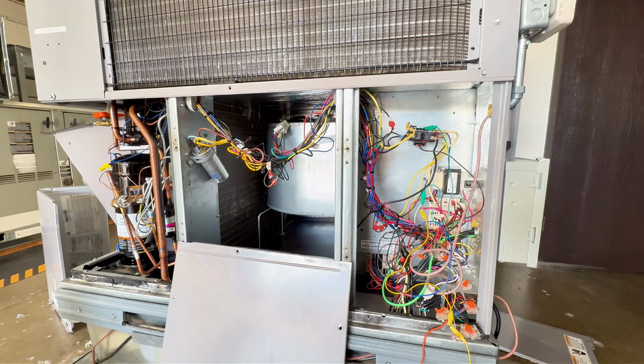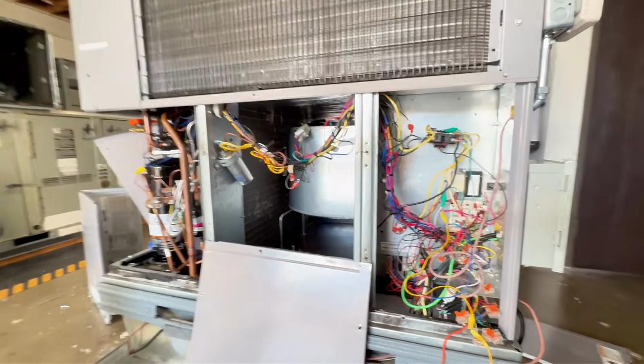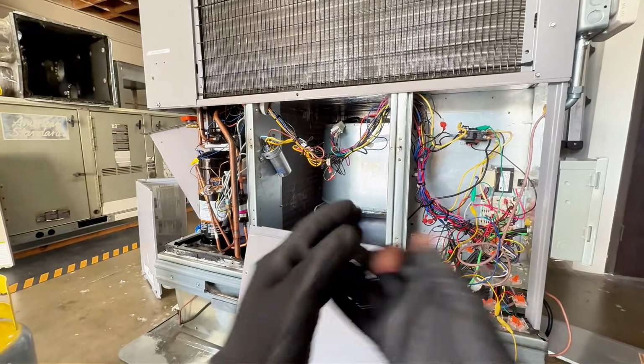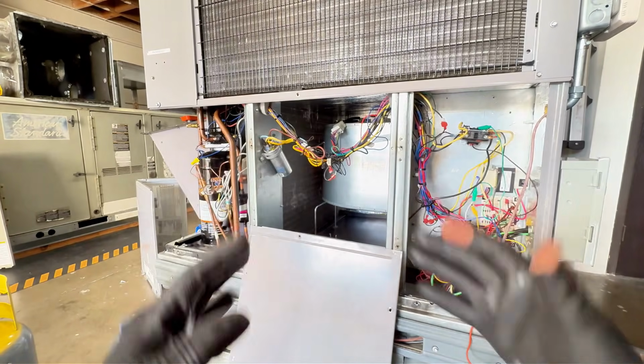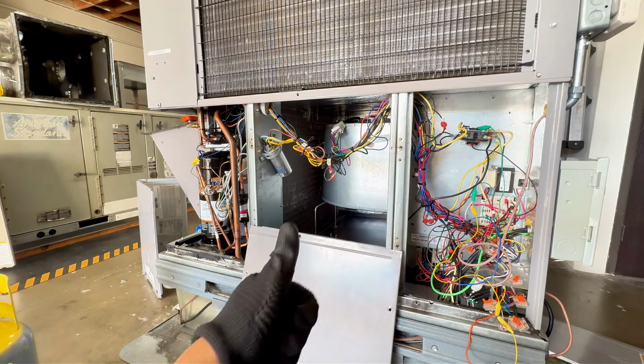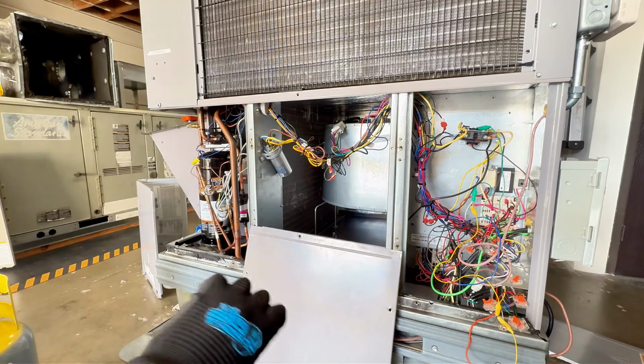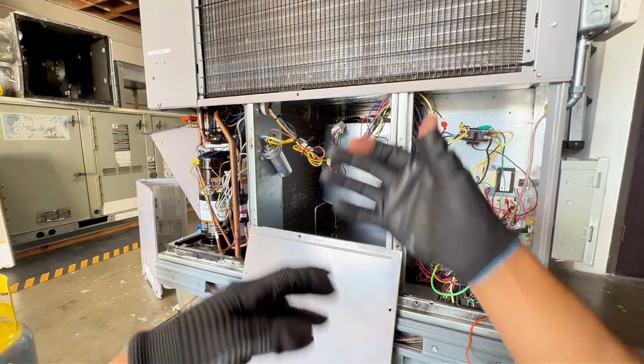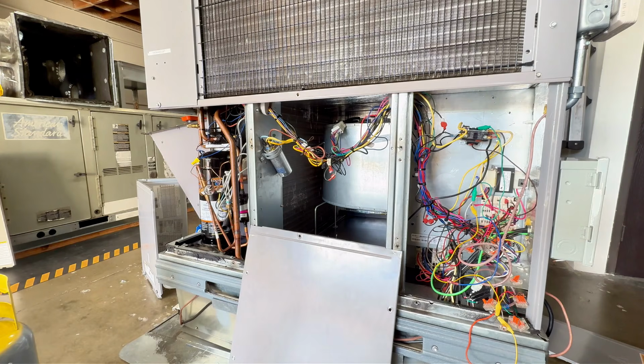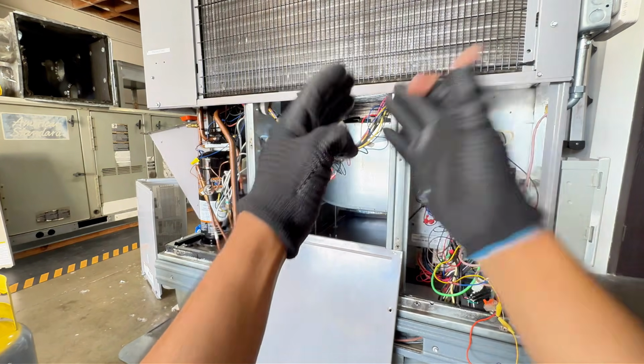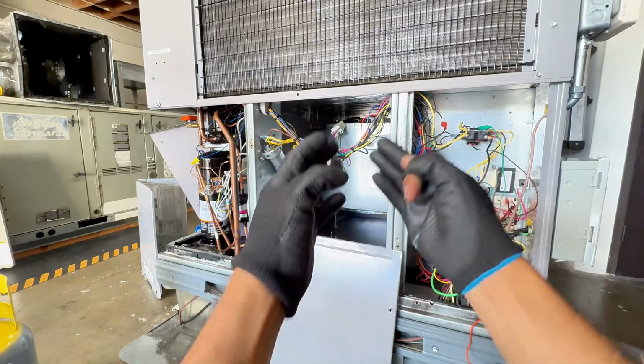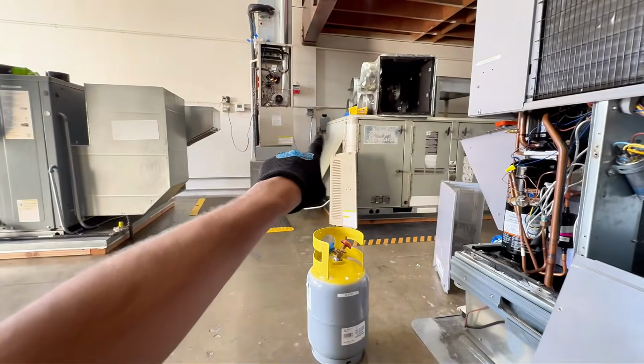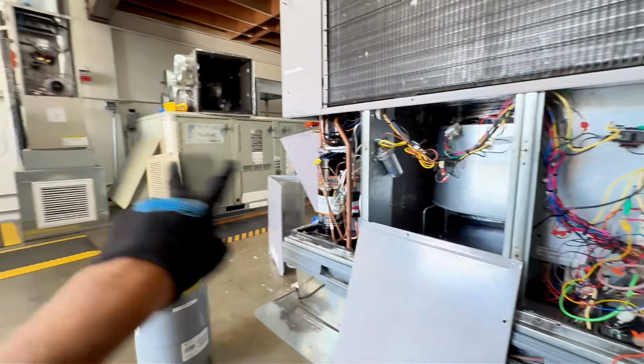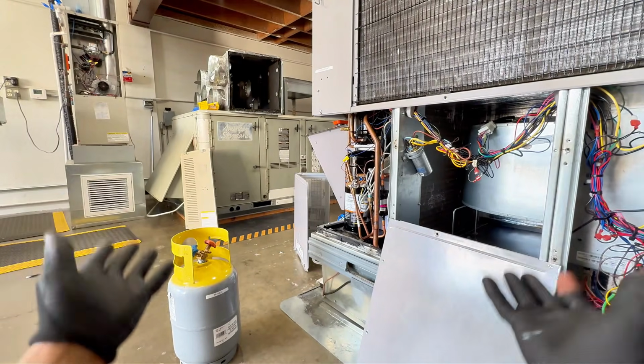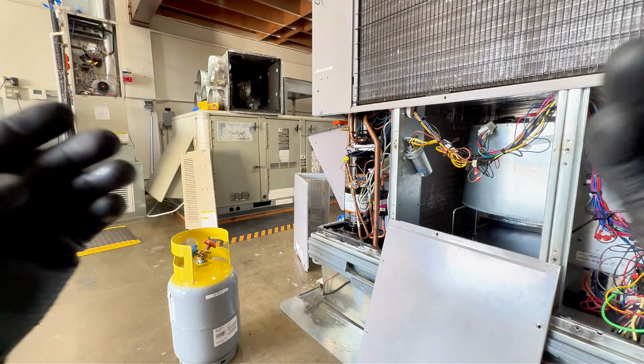Question number 4 had to do with airflow. So what's going to happen on a system where you have an air restriction? Are your amps going to go up or down? Is it going to be working more or working less? So remember, this one here has an ECM motor, and that one there has a PSC. We're going to test both. So which one's going to pull more or pull less with the restriction?